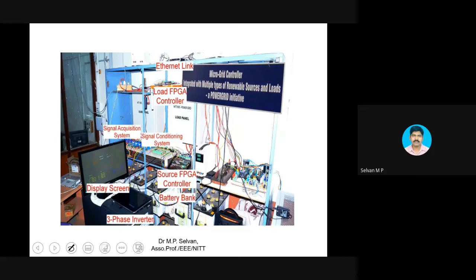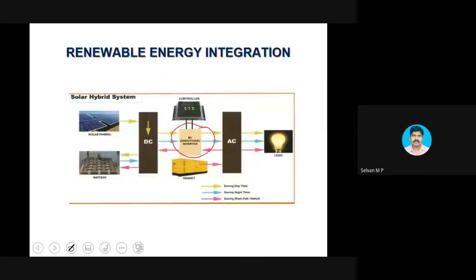If such inverters are in grid mode, there is no problem. Grid is there, so even if your load increases beyond what solar generation can meet, the grid will supply that. But in off-grid mode, energy balance or power balance is very important. Whatever is the generation, only that much load should be connected, otherwise there will be voltage and frequency issues.